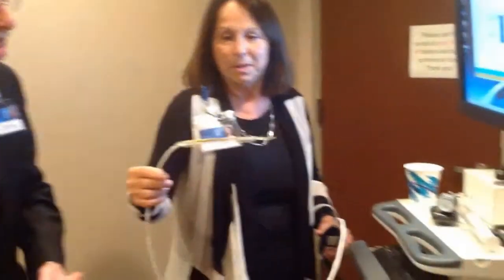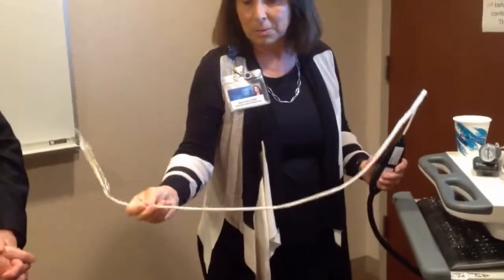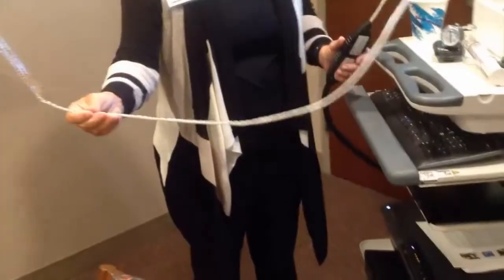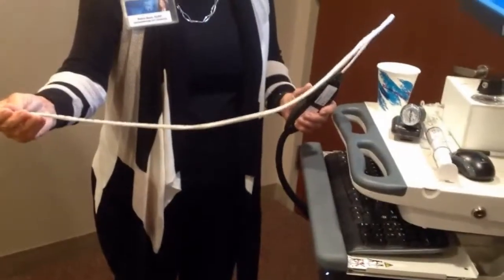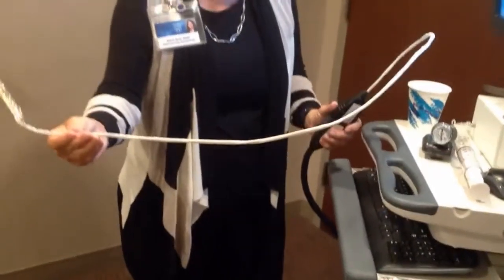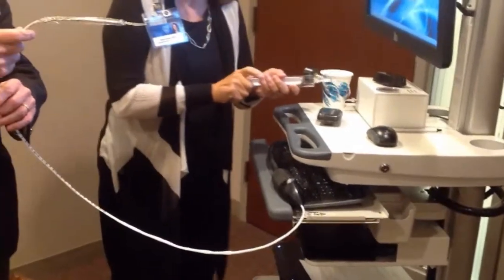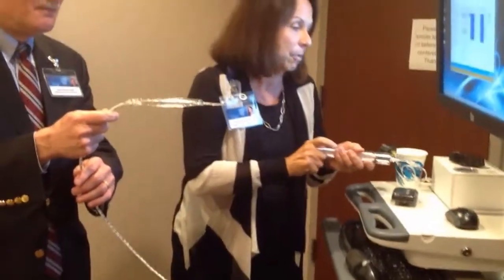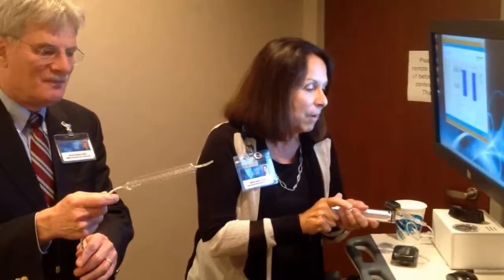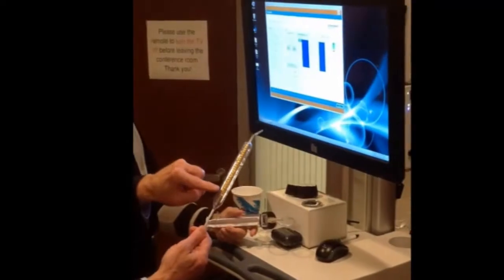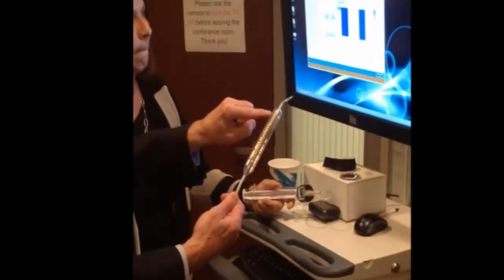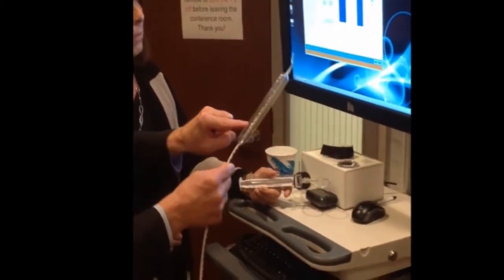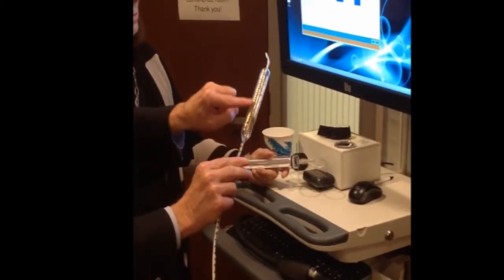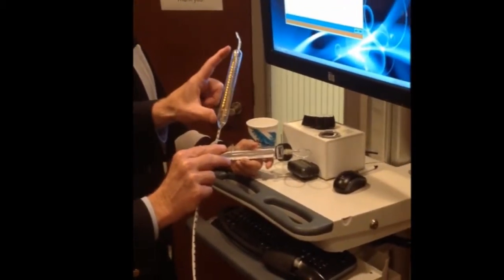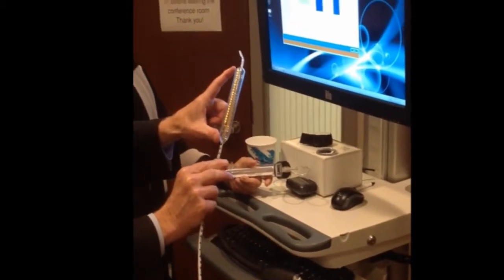So this is the probe, the impedance probe. As you can see, it's marked by centimeters. So Dr. Katzka, after he does the endoscope, he measures where the GE junction is, and then we place the probe. We usually inflate for our narrow esophagus for patients with EOE to about 5 psi. Here's the probe suspended in air. Here are the electrodes. We have 10 electrodes on one side of the balloon and the other side of the balloon. Again, this passed through the esophagus, so measuring at least 10 centimeters of the esophagus.